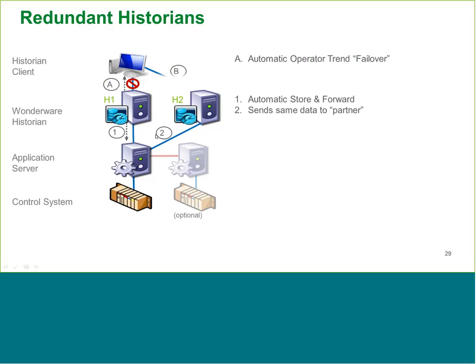We also provide redundancy for the operator, so that if they're doing historian trends and their historian goes down, the trend automatically fails over to the redundant historian. So we have both levels of redundancy here, on the data collection side and on the data retrieval side. And again, these are all built into the Wonderware products these days - it doesn't require any custom scripting or custom development.